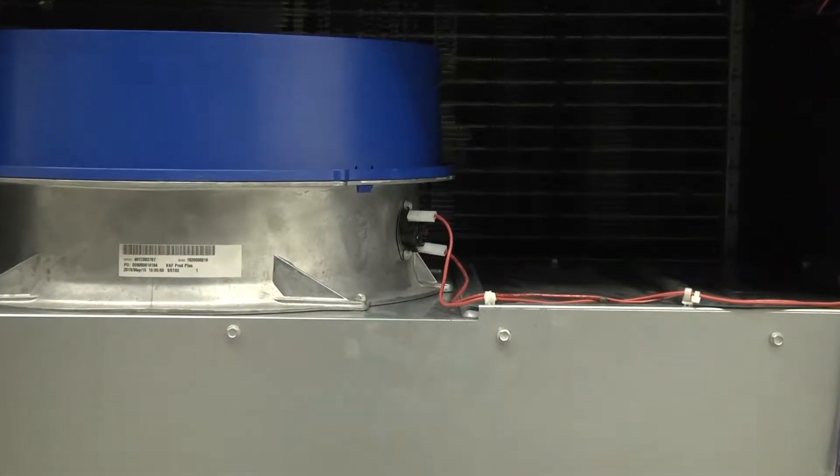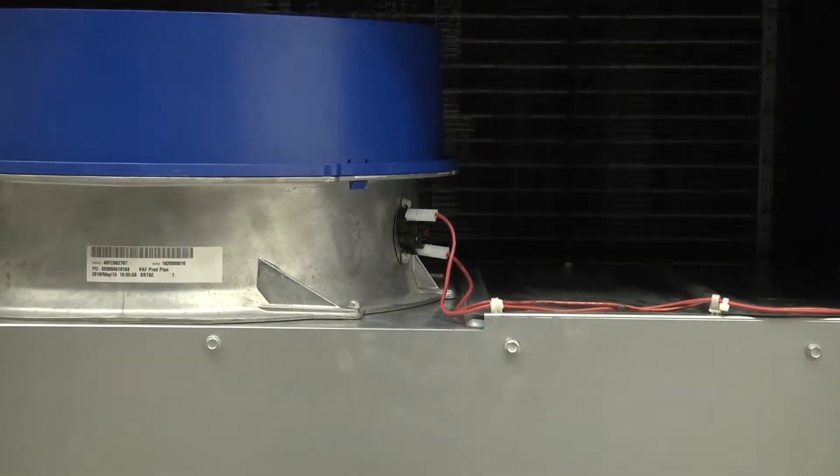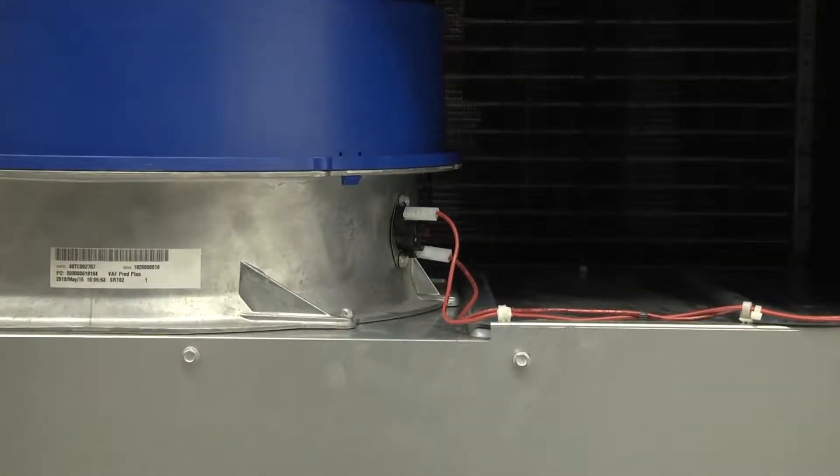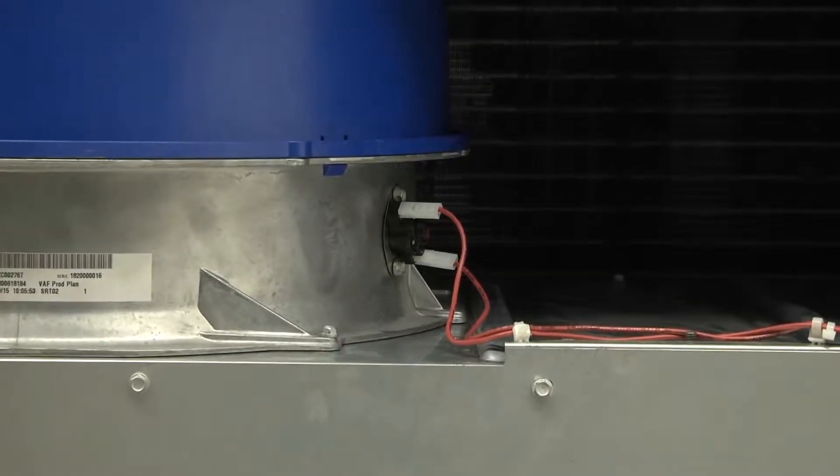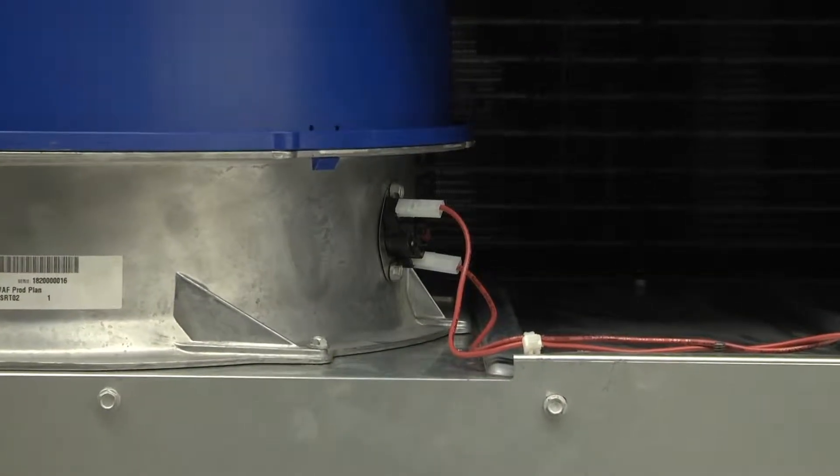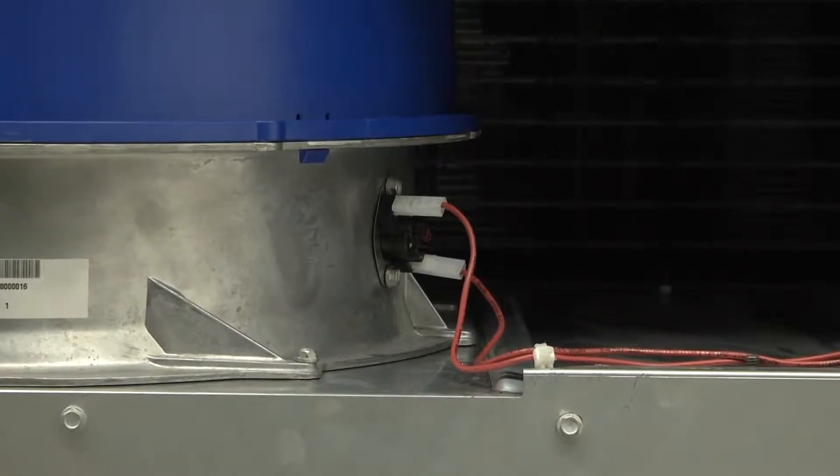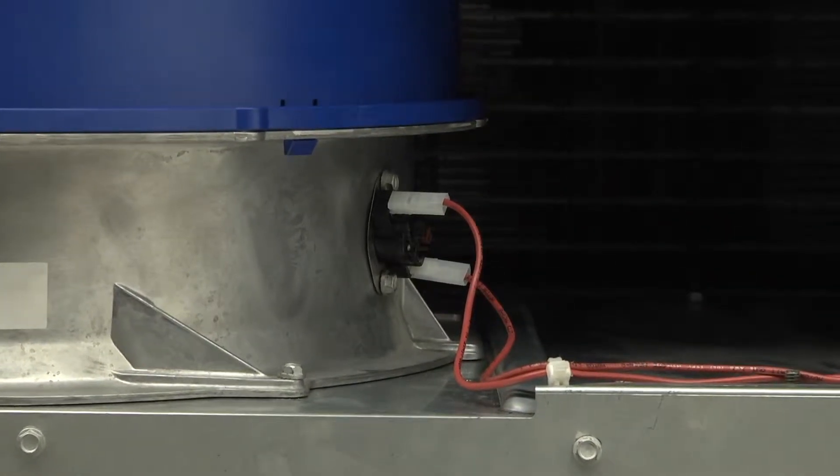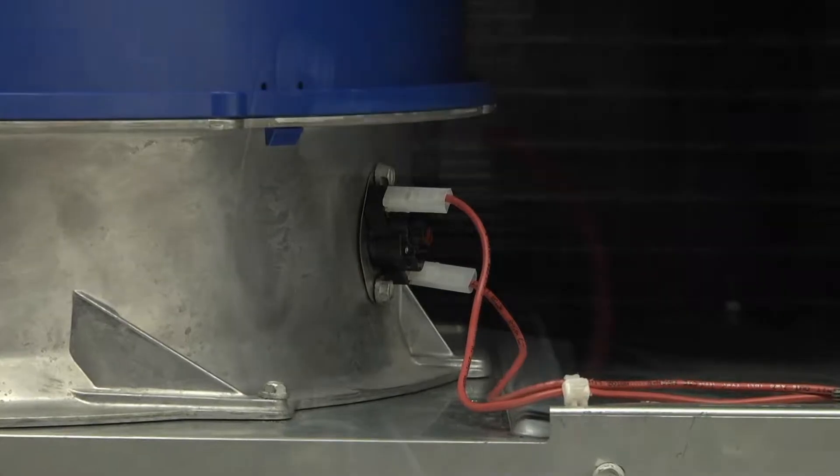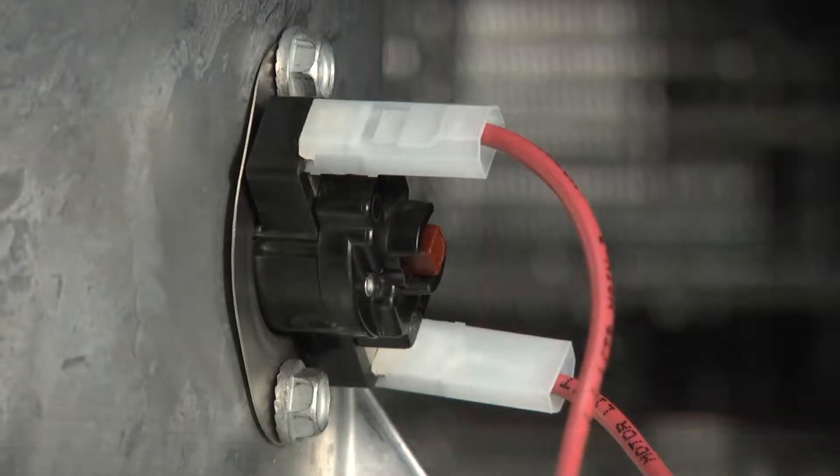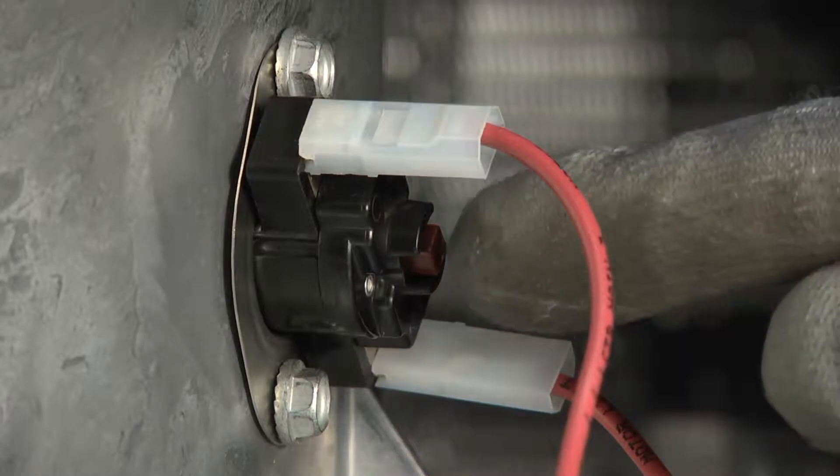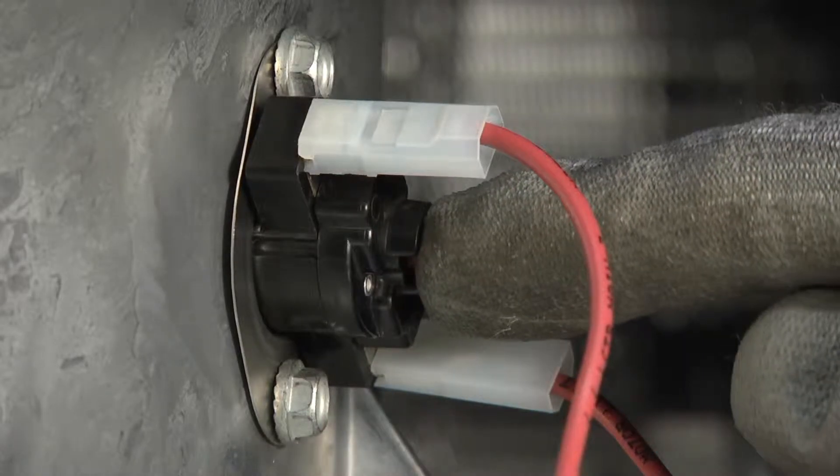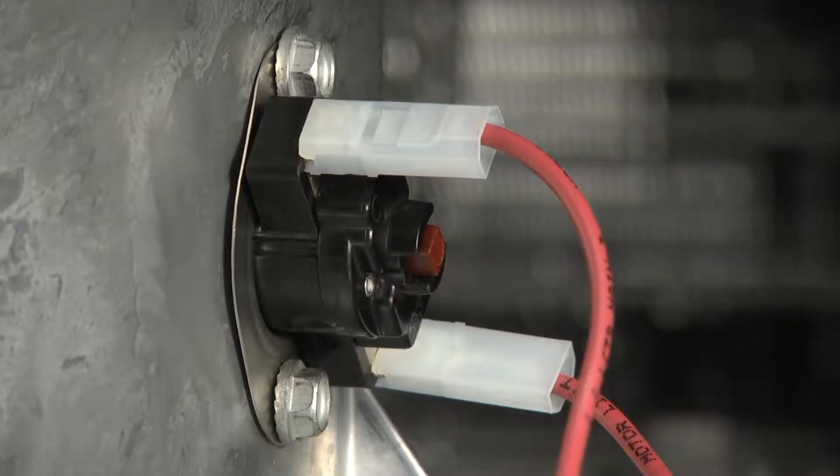One other thing to point out is that the stator temperature limit switch located on the indoor fan casing is a manual reset limit switch. So if the temperature gets too high and it trips, you'll need to physically press the red reset button to reset it once things have cooled down and any issues have been addressed.